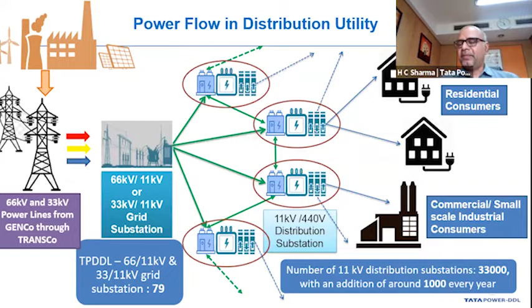So going further, the next thing we have done is that we have converted from AIS to GIS. This GIS substation was one of the things where you require low maintenance, number one. Number two, you save a lot on the scarce resource of space. You can see the normal substation, which is AIS, at the 66 kV level takes a space of around 80 meter by 80 meter, around 6,400 square meters. Whereas if you go for the GIS of the same capacity, it would take around 1,500 square meters of space. So around 75% saving, or you can say that GIS takes around 25% of the space which an AIS takes.